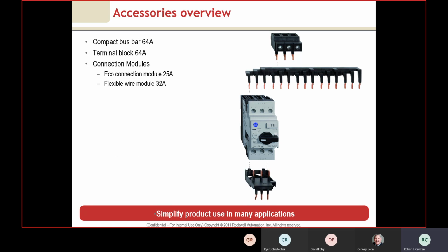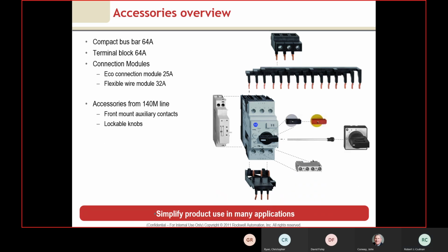We also then have the connection modules we talked about before to allow the connection to the bottom. This also gives us the flexibility of adding the auxiliary contacts, and we've got the ability to do a lockable knob on the front end. So a lot of flexibility here in a small system. And when we tie this all together, we can get it to meet the UL 489 branch protection that's required in a lot of applications.